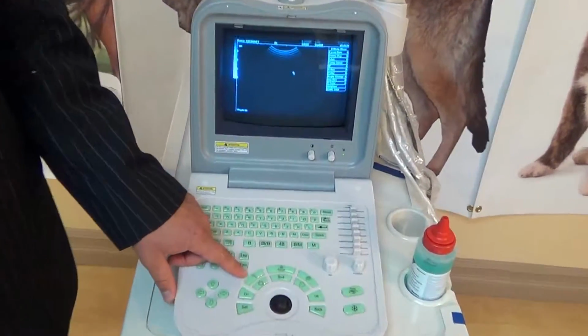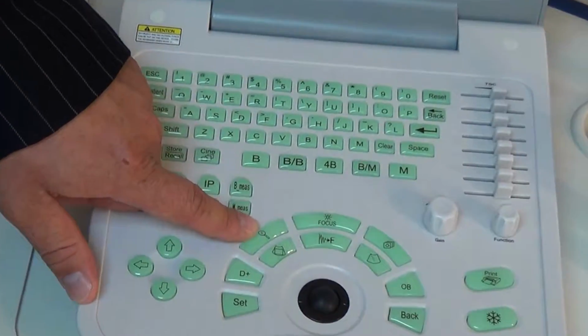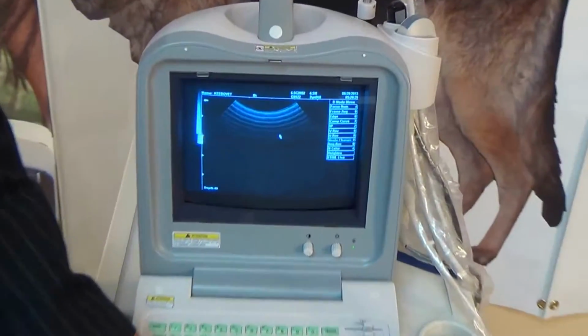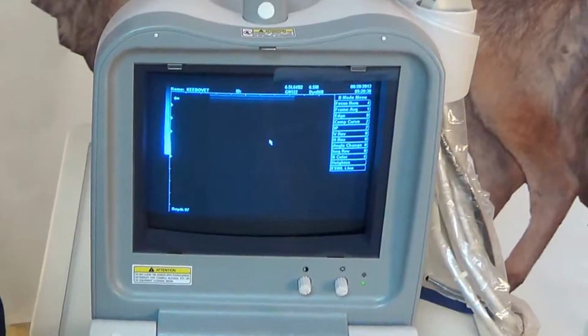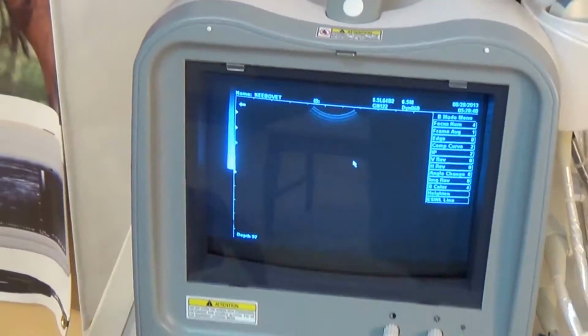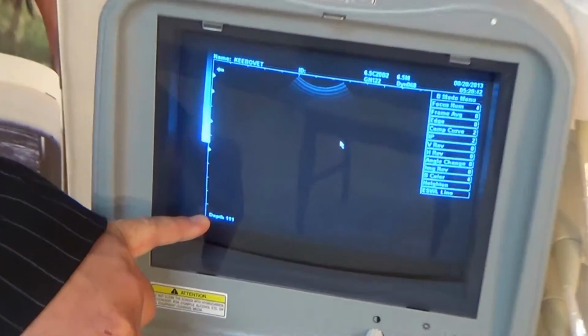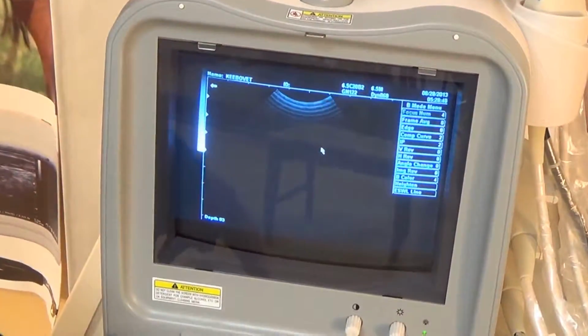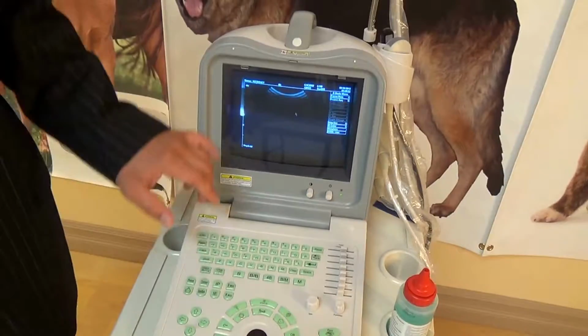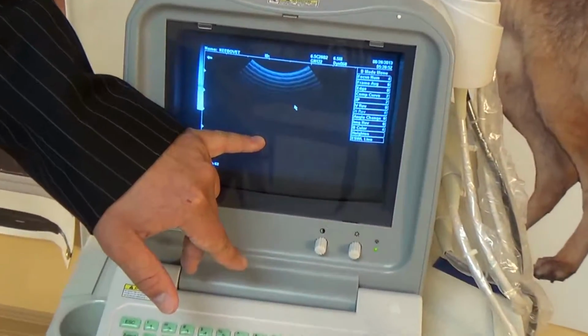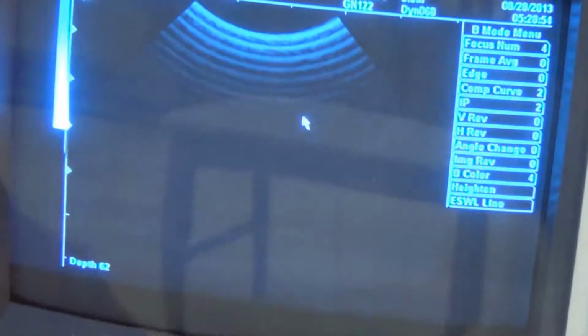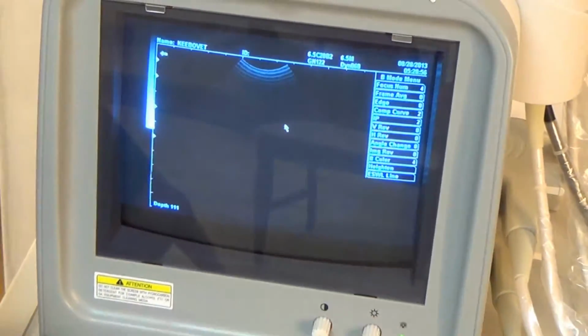Moving along, there's another simple button. This is kind of like a zoom button, looks like a magnifying glass in my opinion. This will control your depth. So you basically use it to take the depth all the way in or all the way out. And you can see the depth control here, and I believe that's in millimeters, so you'll come down, it converts to centimeters. And so you just zoom in if necessary for a lesser depth if what you're looking at specifically is in the near field versus the far field. So we'll just go back to the zoomed out setting.